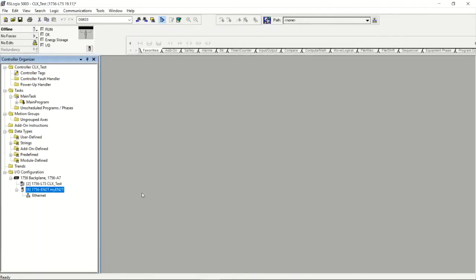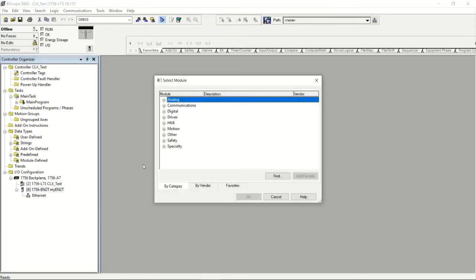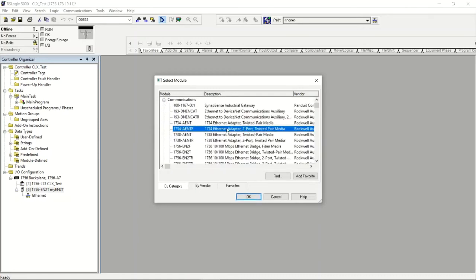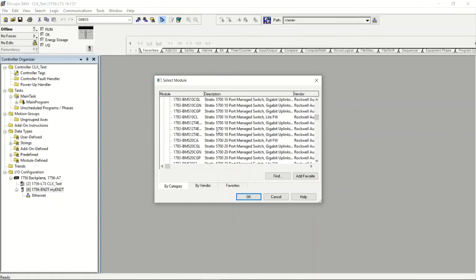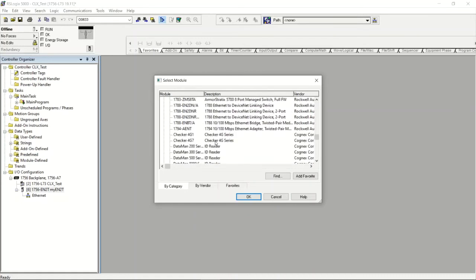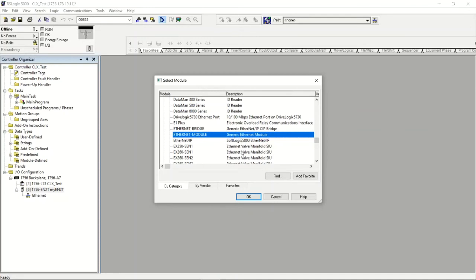Just like in CodeSys, I can now add a child module underneath my Ethernet card — this is where I add the Raspberry Pi / CodeSys PLC. Rockwell doesn't have CodeSys listed as a standard device, so instead we use what they do have: a Generic Ethernet Module. I'll find it — 'Generic Ethernet Module' — and say okay.